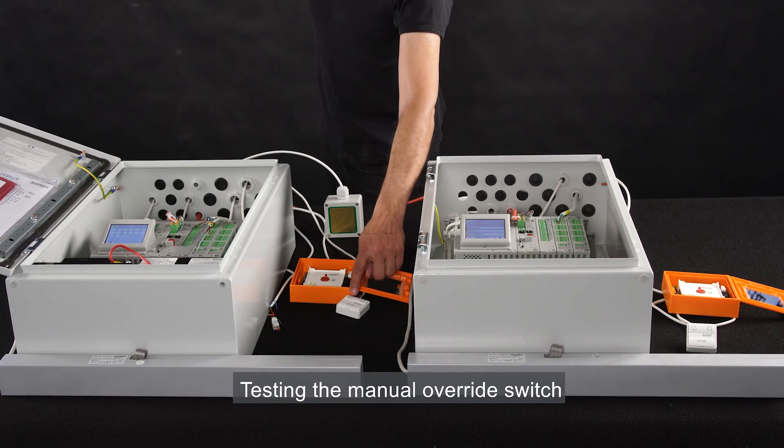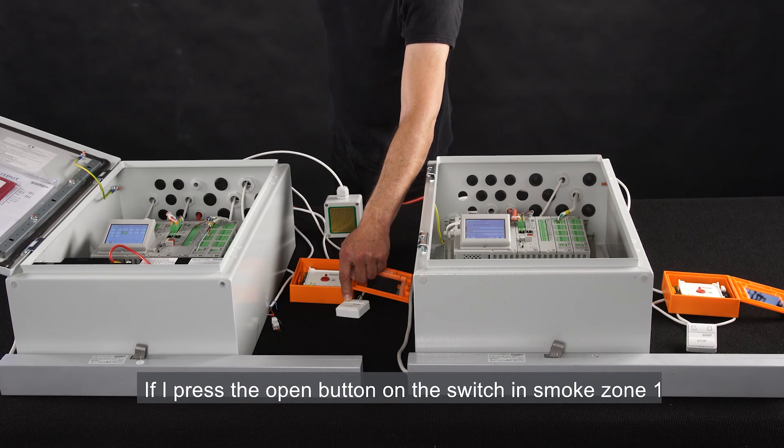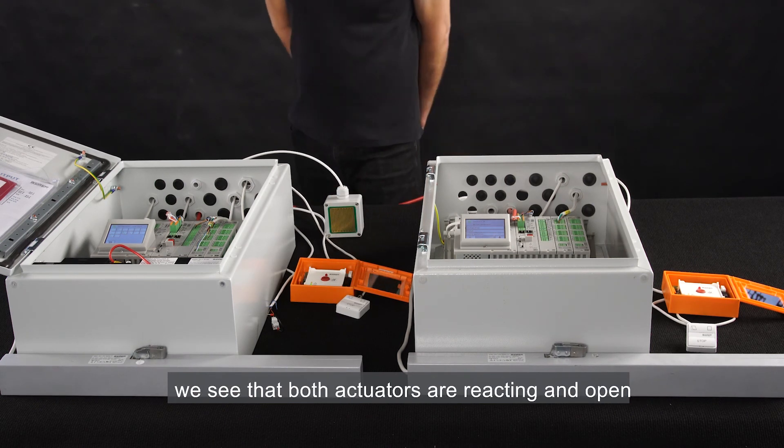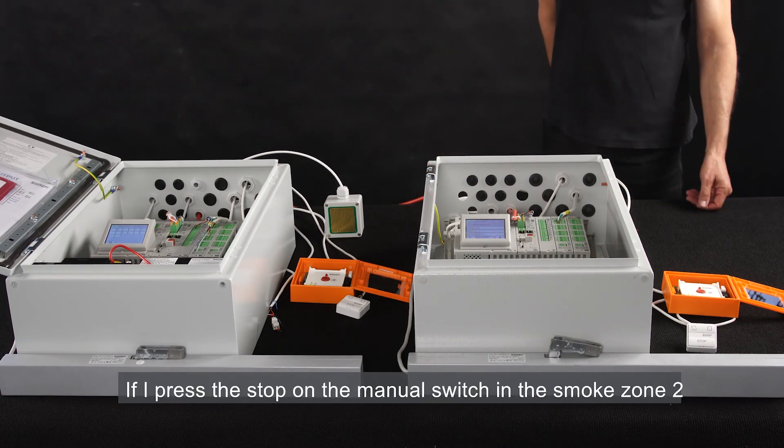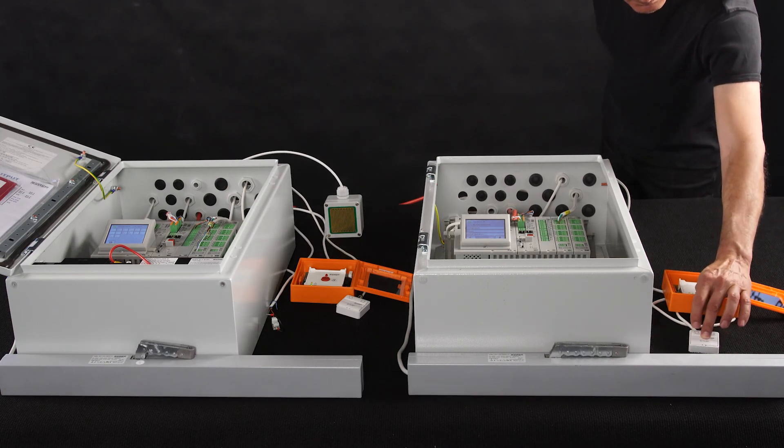Testing the manual override switch. If I press the open button on the switch in smoke zone 1, we see that both actuators are reacting and open. If I press the STOP on the manual switch in smoke zone 2, both actuators stop.